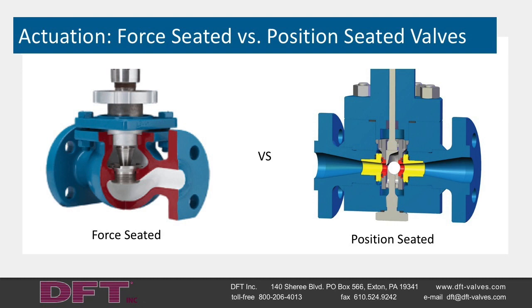Actuation: force-seated versus position-seated valves. Rising stem valves, such as globe-style and Venturi-style control valves, require different types of actuators than rotary ball-style control valves. A globe-style valve requires actuators that can generate enough force to drive the plug into the seat in order to overcome the forces due to pressure in the flow stream — this is called a force-seated design. Severe service valves are typically associated with high pressure, requiring high seating force. The higher the pressure, the greater the force required to achieve shutoff, which can result in large and expensive actuators.